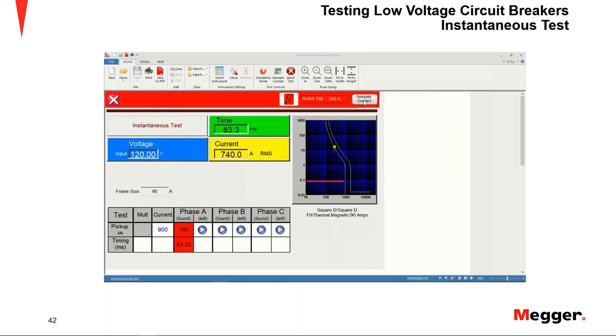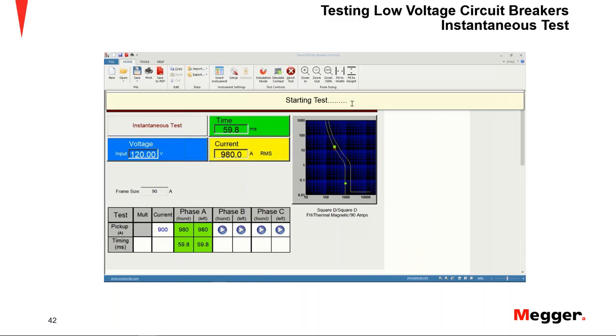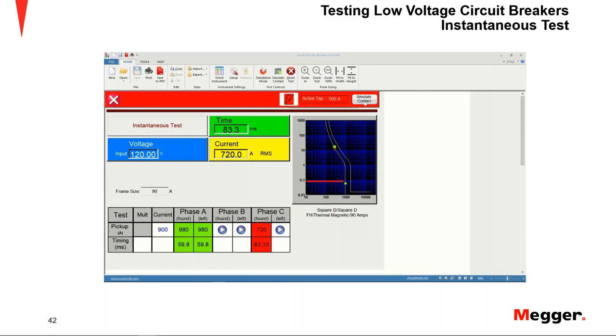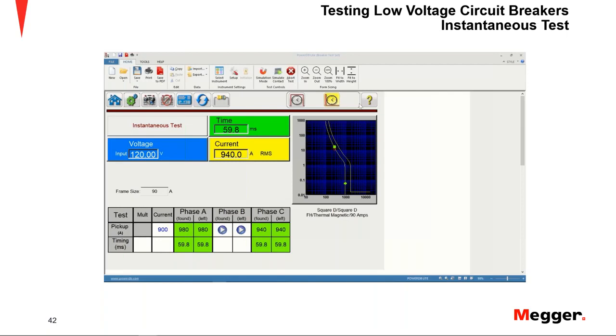Now, different from the long time test, right now our arrow will be horizontal as the unit is doing pulses. If you pay attention to the current indicator, the current is slightly going up each cycle. Also the time, you see, it looks like it doesn't change because the unit again is doing pulses. You can change that in the settings. I was using 5 cycles on, 100 cycles off. So again, the unit will keep doing those pulses until the breaker trips, right? So that's why you see the horizontal line, and you can see that it's slightly increasing. And you can see also in the yellow current indicator how the current is going in steps of 20. You can also change that step configuration in the settings, right?